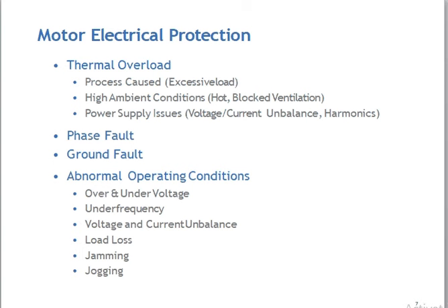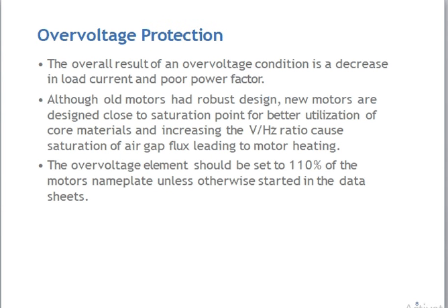You can see this overvoltage fault. This overvoltage fault decreases the load current and gives poor power factor. In olden days motors were robustly designed, and nowadays motors are designed close to the saturation point, with better utilization of the core materials and an increased V/F ratio. Also, we are designing the protection for 110% of the voltage. We are setting the set value at 110% of the rated value.